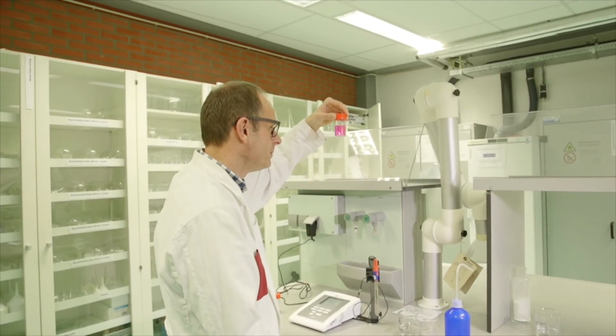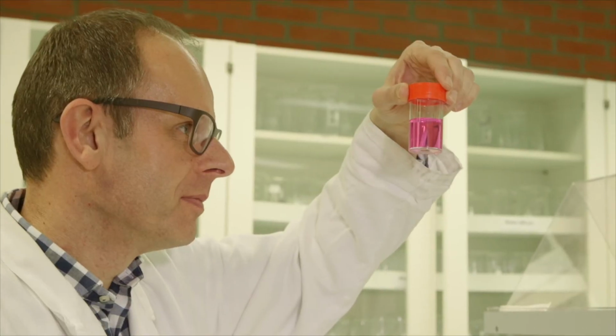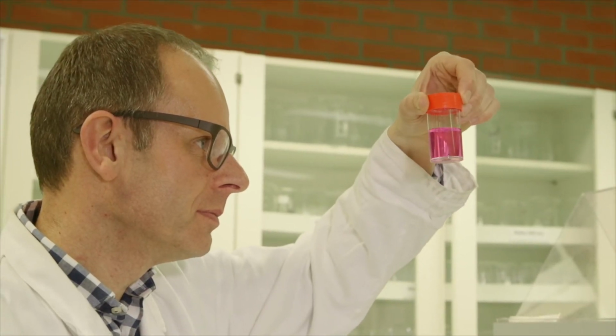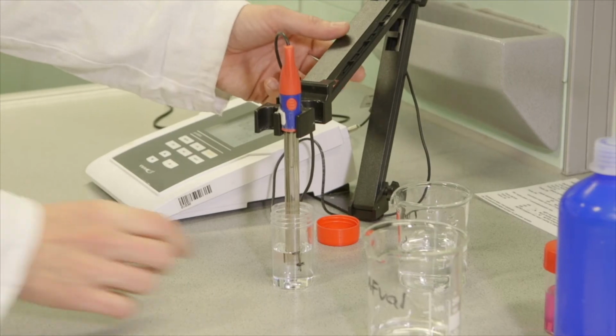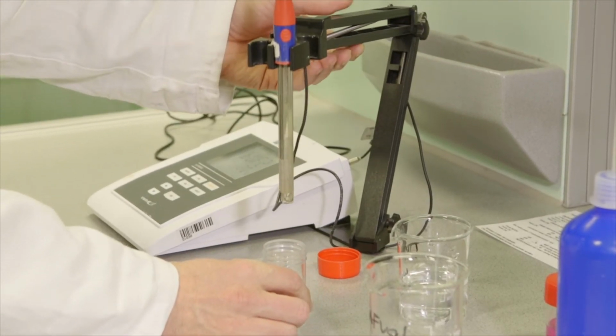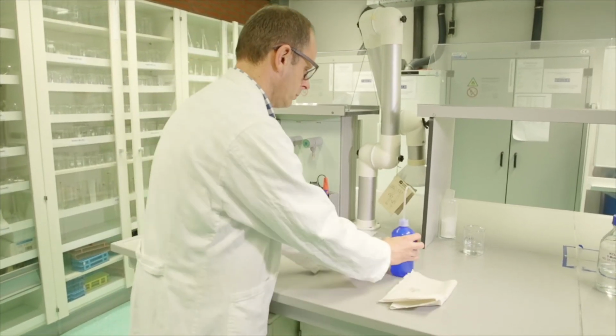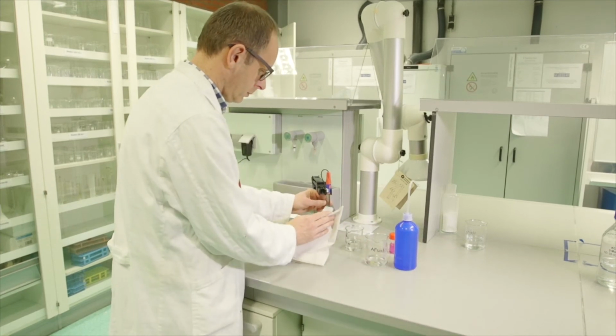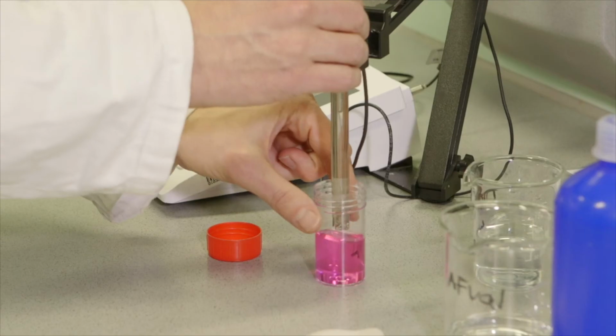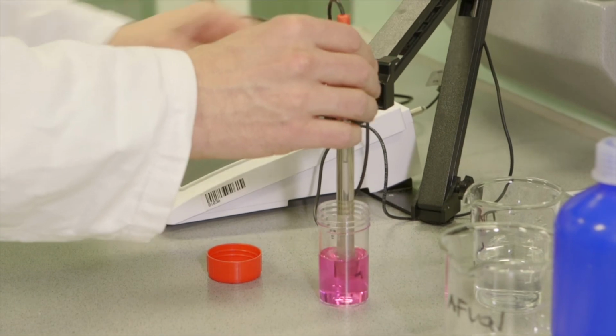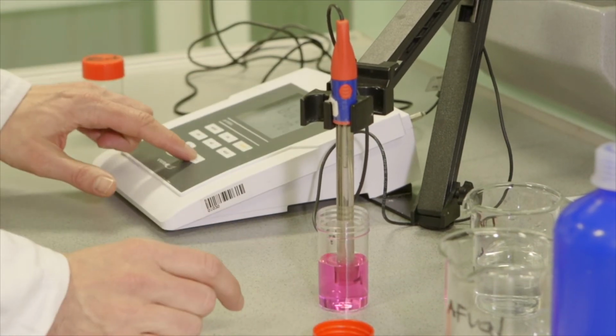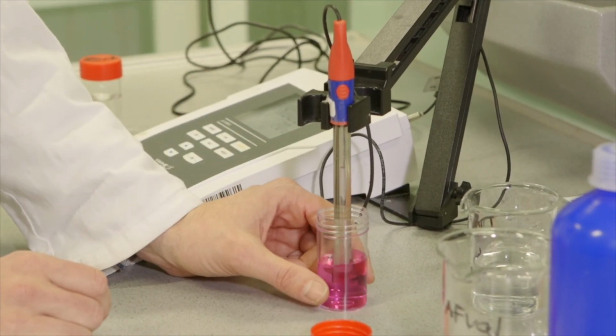Check the buffer carefully again. If there are particles floating in it or the colour is strange, discard the buffer and take a new one. Remove the electrode from the pH buffer and rinse this with demi-water into the waste container. Dry the electrode and place it in the pH 4 buffer, then press the OK button. If the word auto is flashing, the device is busy.